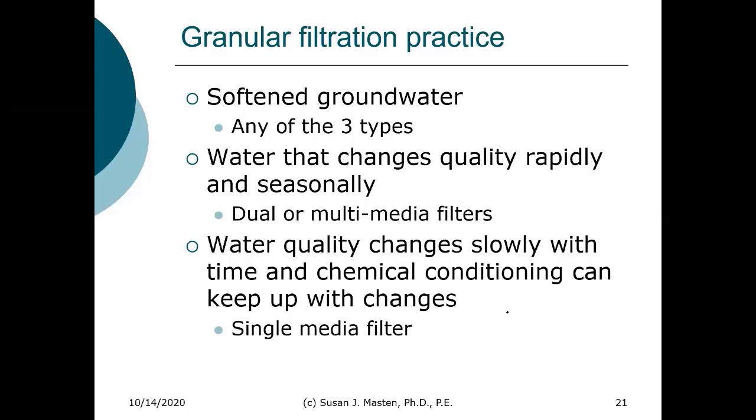On the other hand, Ann Arbor uses a combination of groundwater and Huron River water. The Huron River water is going to change. Water quality will fluctuate rapidly with storm events. It'll change with changing temperature. So a dual or a multimedia system makes more sense there.